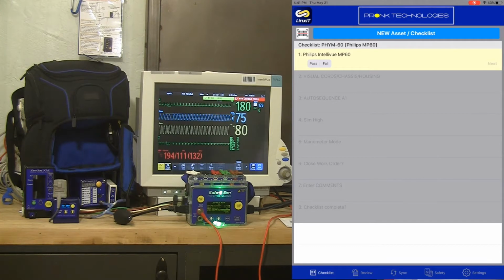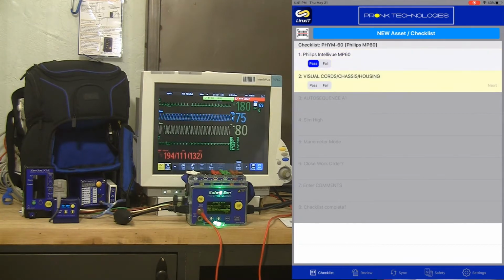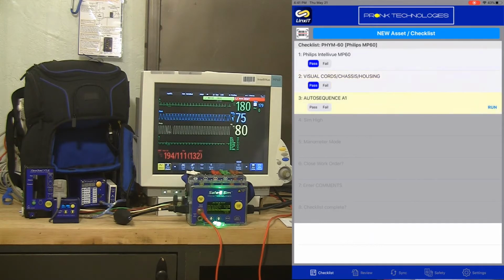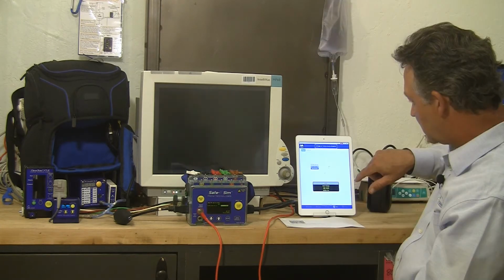Step 1 is to confirm that it's a Philips IntelliVue. Step 2 is to do a visual inspection of the power cord and chassis. I'm going to hit pass. Step 3 is to run an auto sequence, and in this case, I'm going to hit run.